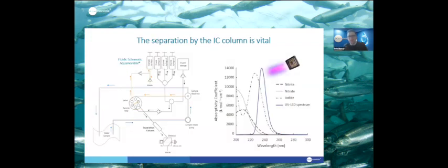We look at our system in a little bit more detail. Essentially, using rapid ion chromatography, we overcome those issues because we have the selectivity for nitrite and nitrate. The mobile phase passes through the system. Sample is introduced into the mobile phase. Everything passes into an anion exchange column. It enters into our UV LED detection system, and we use a 235 nanometer wavelength LED, which allows for the direct absorbance of nitrite and nitrate.